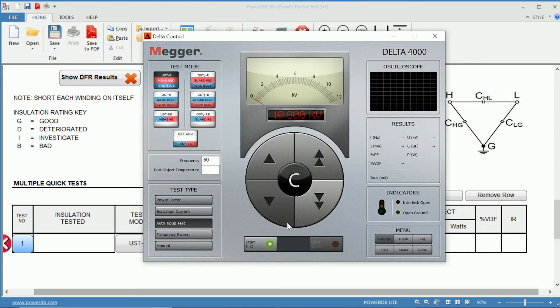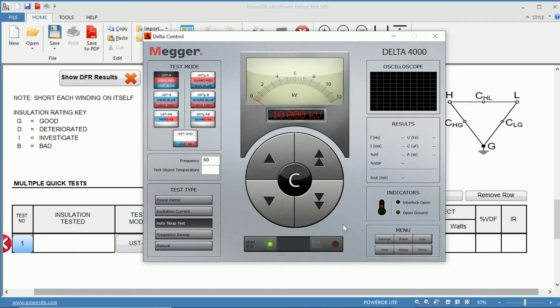Now that we have that selected, if we start this test, it would increment in 1 kV steps, up to 10 kV, and that would be our tip-up test.